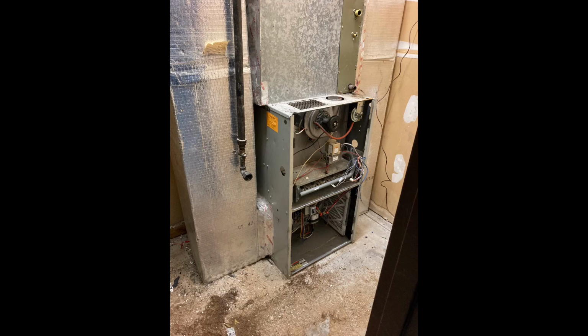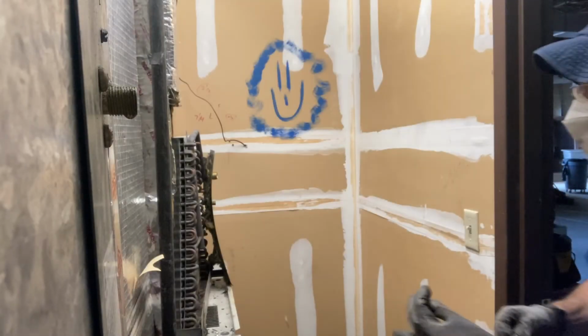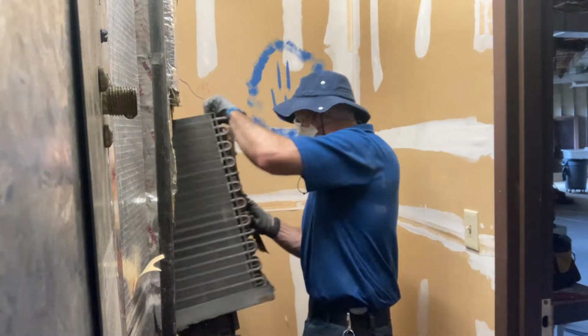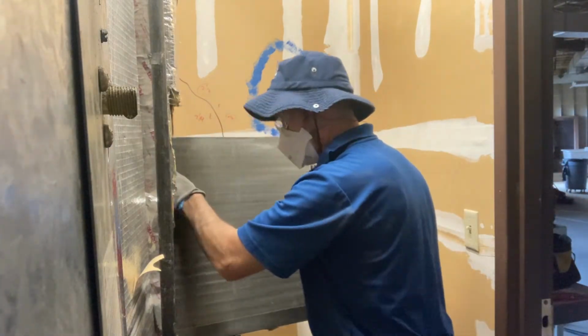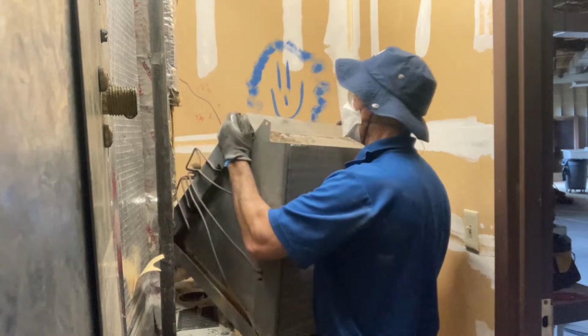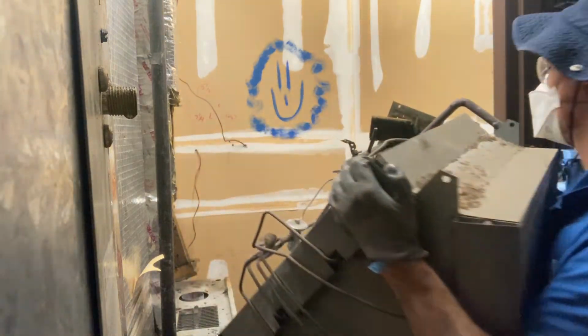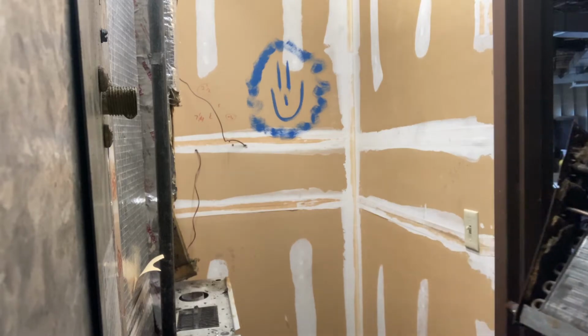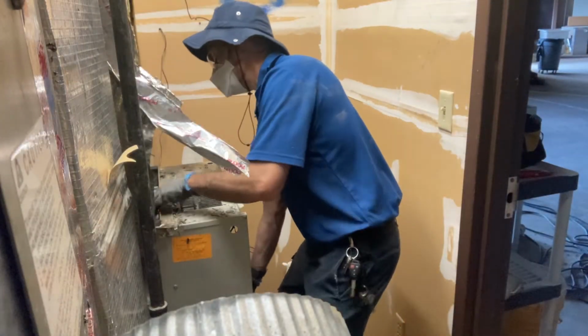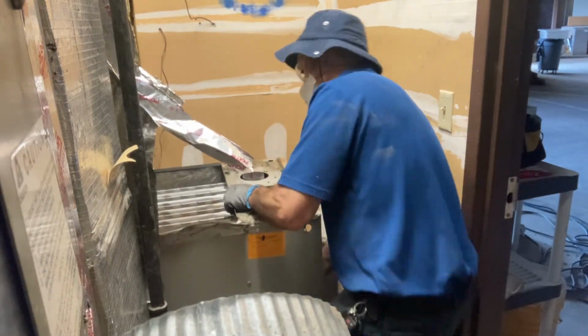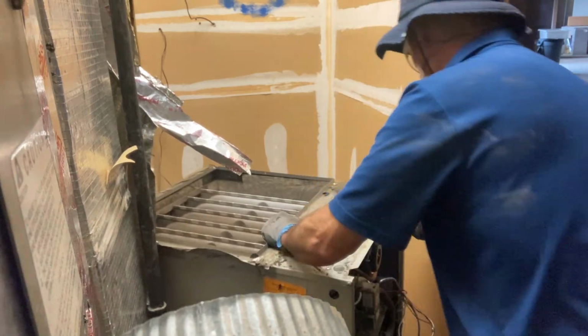Now that we're done on the roof for now, I'll go downstairs, turn the gas off, turn the power off to the air handler, disconnect, and remove the old air handler. So we've disconnected the vent pipe, the gas line, and the electrical. With the plenum disconnected, I'll go ahead and pull out the old A coil. The A coil gone, we'll go ahead and pull out the old air handler. Wear gloves and watch out for sharp edges.